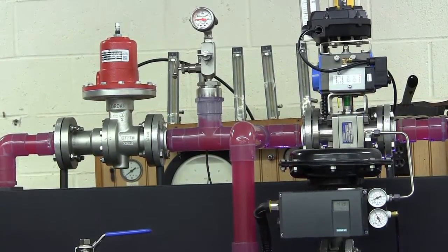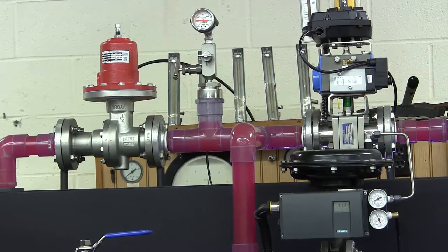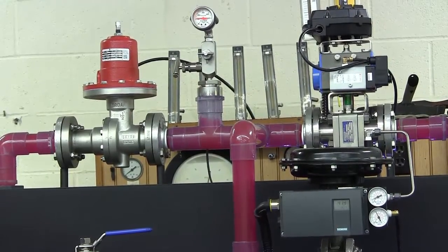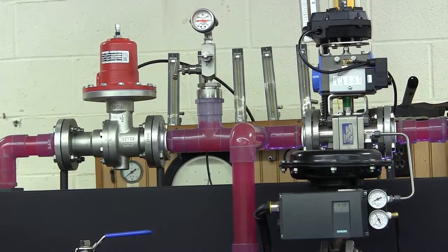The valve will modulate to maintain the pressure at 10 psi. When the upstream pressure falls below the set point, the mark 50 will return to the closed position.